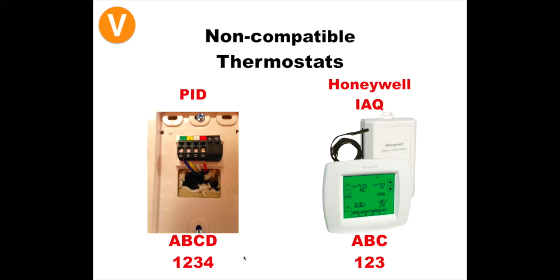On the Honeywell IAQ side of things, these thermostats have a control module that sits in between the furnace and the thermostat, and these actually communicate back and forth. If we connect our thermostat to one of these systems, we can damage that control module, and those can end up being pretty expensive home damages as well. So just remember, on these, it's all about the terminals. You pull the thermostat off the wall and you see terminals that are labeled A, B, C, D or A, B, C or 1, 2, 3, 4 or 1, 2, 3. Make sure we don't connect these. We just can't take these over.